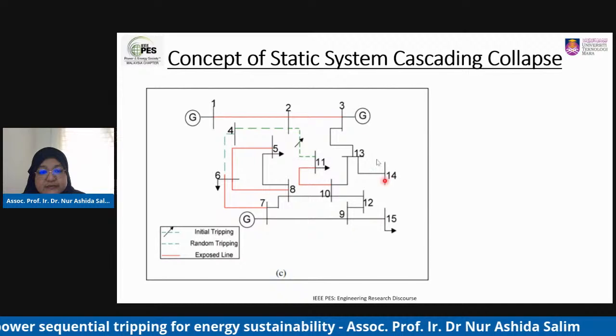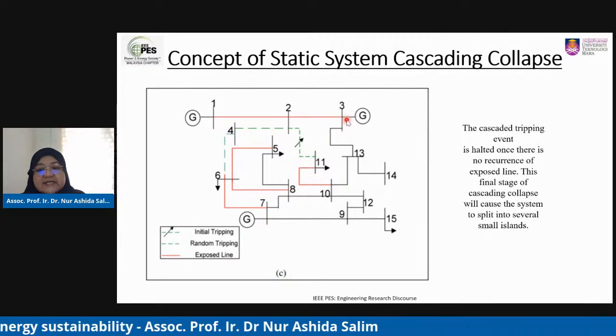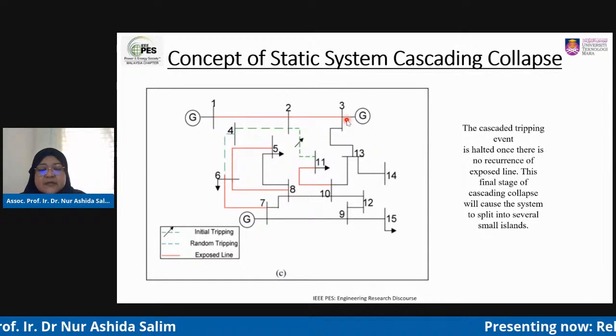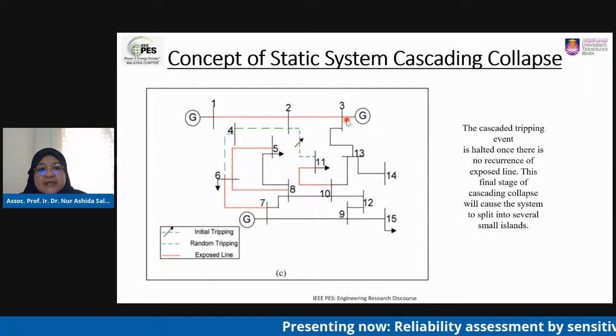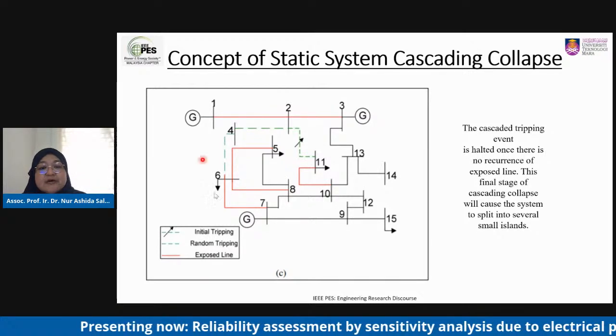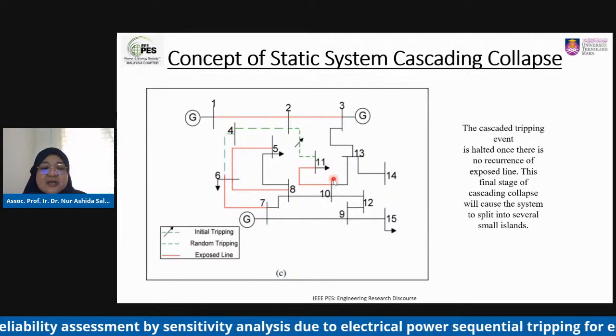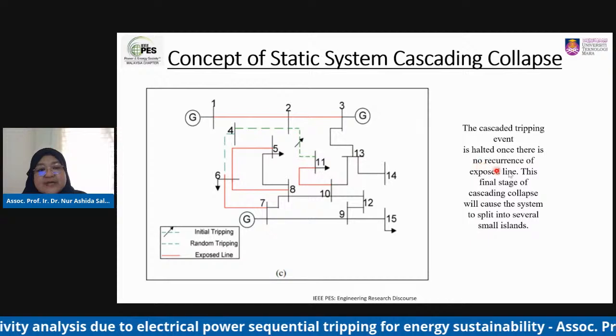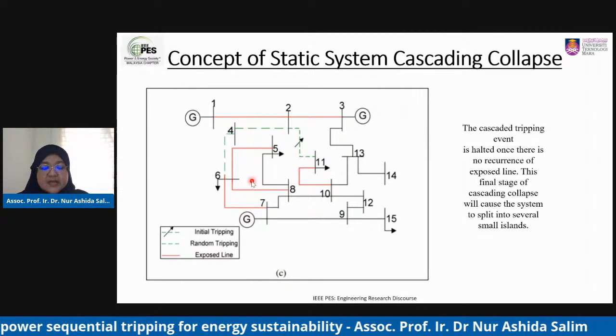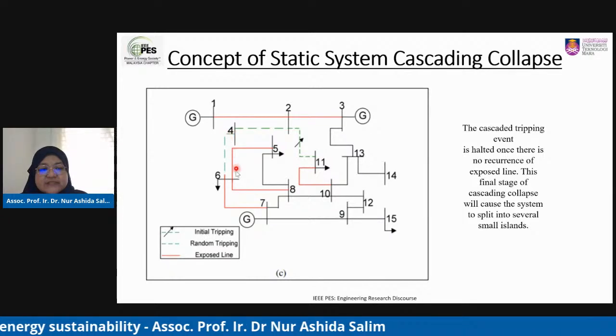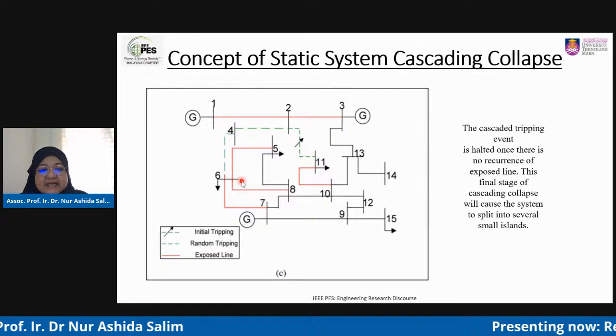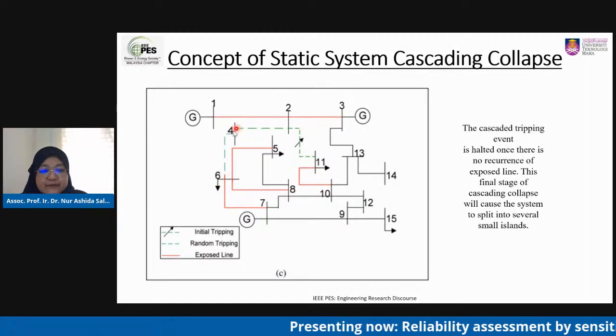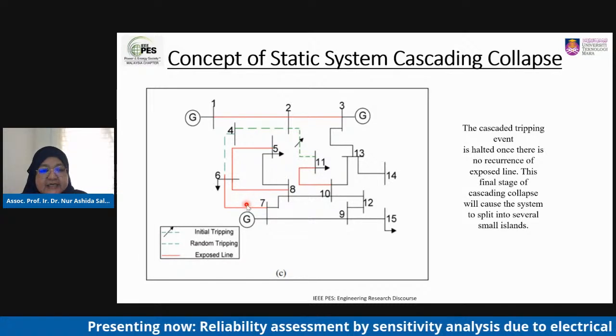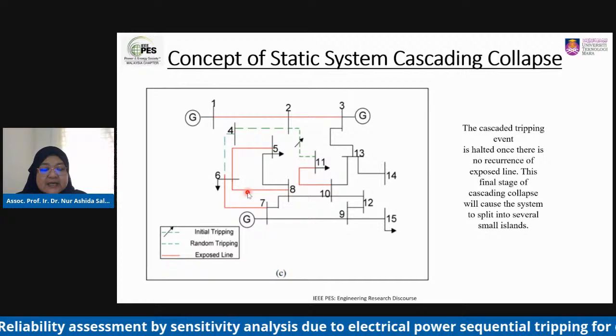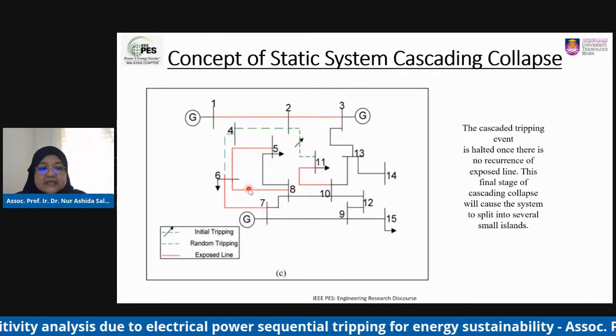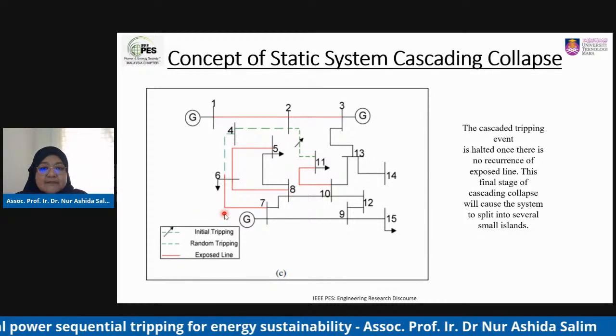All right, so the process continues until there are 2 conditions where this cascading tripping is halted, that means abruptly stopped. The first condition is when the whole system collapses, that means all the transmission lines are disconnected. Another one is that there is no more tripping. So let's say, for example, the third transmission line tripping is line 46. So we have exposed lines at bus 6 and also bus 4. If, after we perform the load flow analysis, the line flow of this particular exposed line does not violate the thermal limit of the transmission line, therefore there is no more line tripping.